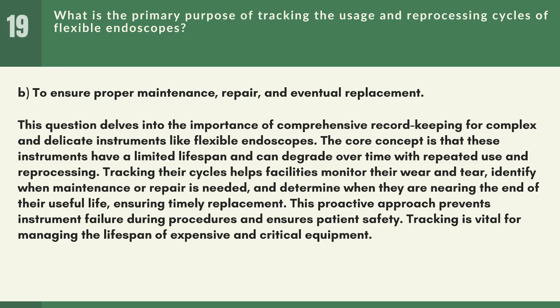This question delves into the importance of comprehensive record-keeping for complex and delicate instruments like flexible endoscopes. The core concept is that these instruments have a limited lifespan and can degrade over time with repeated use and reprocessing. Tracking their cycles helps facilities monitor their wear and tear, identify when maintenance or repair is needed, and determine when they are nearing the end of their useful life, ensuring timely replacement. This proactive approach prevents instrument failure during procedures and ensures patient safety. Tracking is vital for managing the lifespan of expensive and critical equipment.